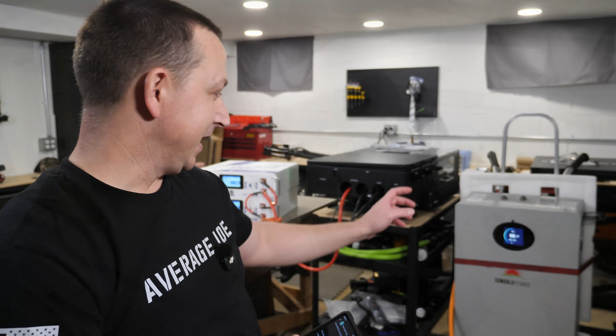Battery number 1, the primary battery, is showing 91% state of charge. It's 73 degrees Fahrenheit, and right in the center you can see our battery voltage is 50.74. We're pulling 96.3 amps, so if we do this for 1 hour we're gonna drain the battery down to 0% state of charge. Next to that is 4,892 watts. So we're kind of at the max of this battery right here.